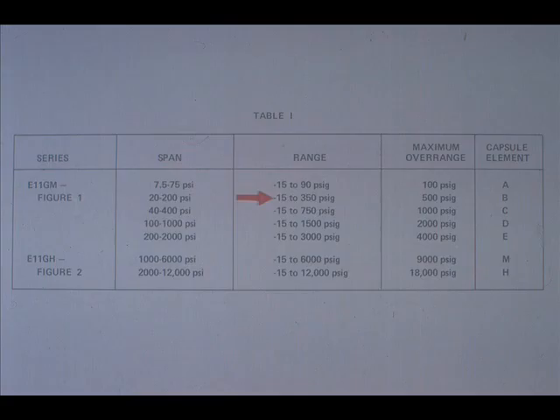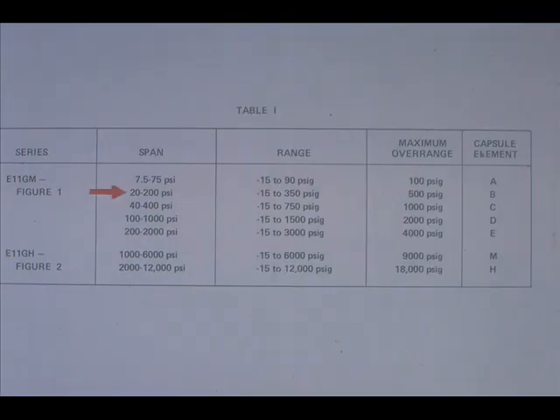The range limits are minus 15 to 350 PSIG. This is within our 100 to 200 PSIG range. Look at the span limits for capsule B. They are from 20 to 200 PSIG. This is within our required span of 100 PSIG. Capsule B will be suitable.